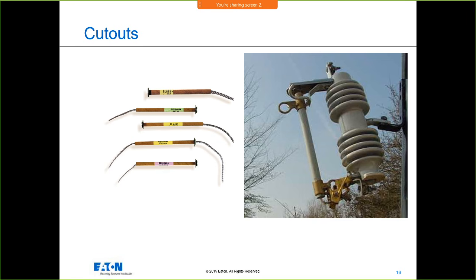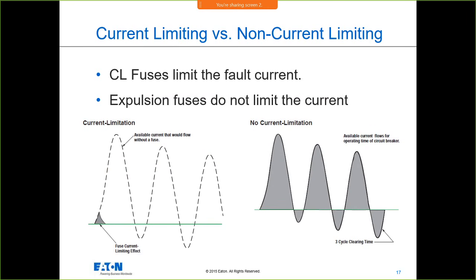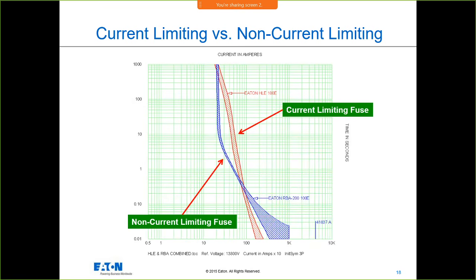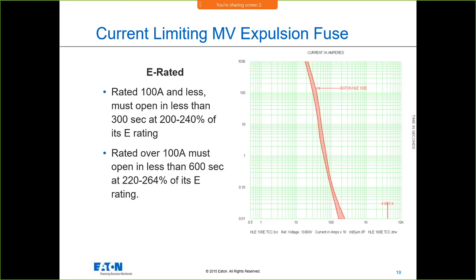Again, you'll have your current limiting and non-current limiting fuses. Current limiting is very similar with regard to the capabilities of this device. You're going to clear that within a quarter cycle. A non-current limiting device is going to let those cycles flow, and that's a lot of energy and a lot of magnetic forces. When you look at the two different types of curves, that's where it's all shown. You have your non-current limiting fuse and your current limiting fuse.